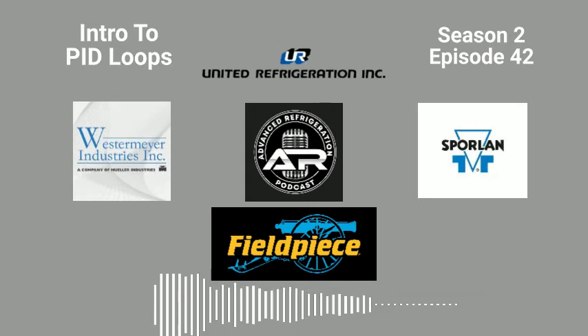So if it's at 20 and you get to 25, it's going to keep multiplying that value every time the PI loop runs, trying to bring that back down to set point. So the PI loop is only trying to bring things back down to set point. Likewise, if it gets below set point, it's going to take away from that value until it gets back to set point. Now, the P is just proportional. If there's so much error away from set point, it's going to keep adding. If there's so much error below set point, it's going to keep subtracting until it's back down to 0.